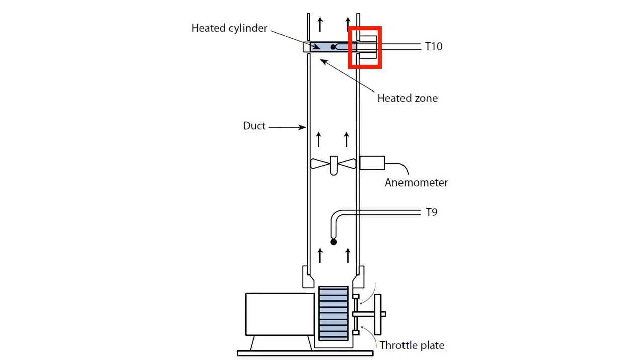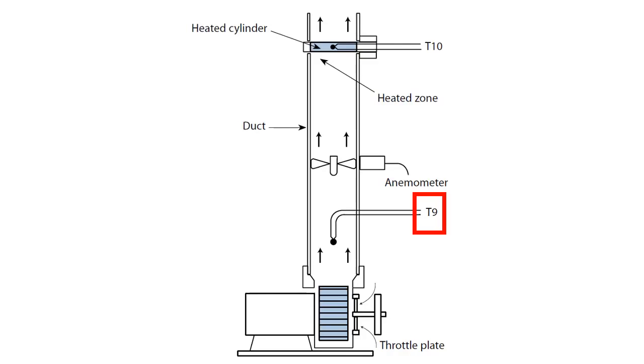A thermocouple T10 attached to the wall of the cylinder enables the surface temperature to be measured. A thermocouple T9 located in the outlet duct allows the ambient air temperature to be measured.